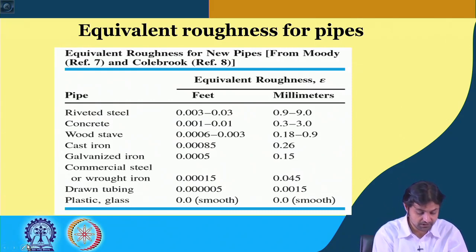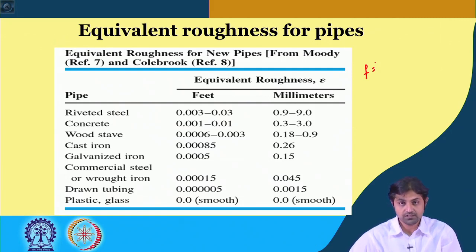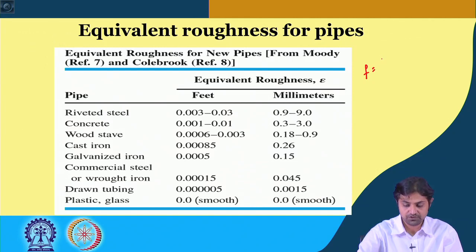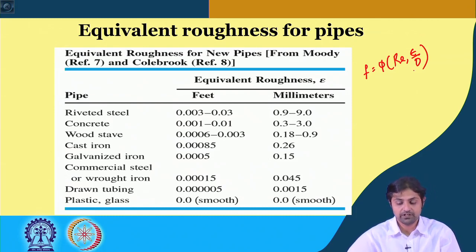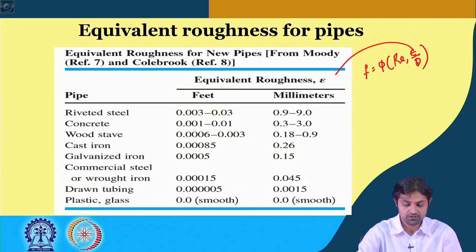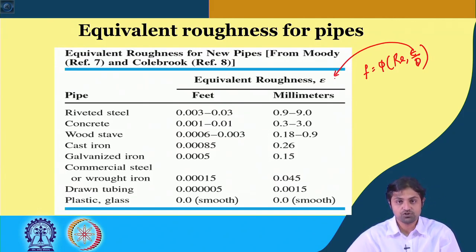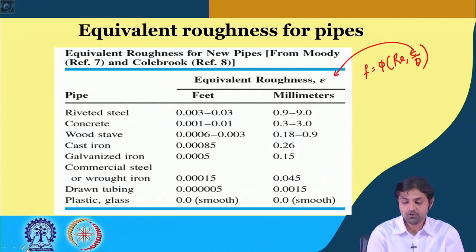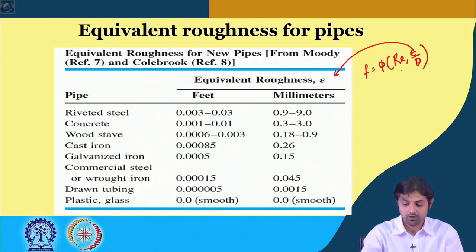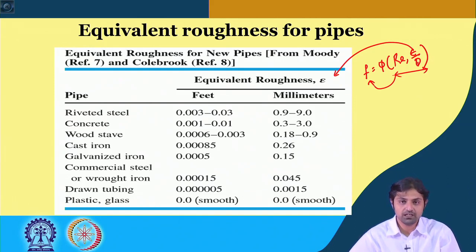Until this point, what are the things that we know? We need to find F, the Darcy-Weisbach friction factor: F is equal to a function of Reynolds number and ε/D. Reynolds number we can calculate if the flow and pipe diameter D are given. Epsilon we can find through tables, and most cases for numerical problems you will be given the value of ε/D directly. If we know ε/D and Reynolds number, the friction factor F depends on both these parameters, and knowing F allows us to calculate the major head loss.